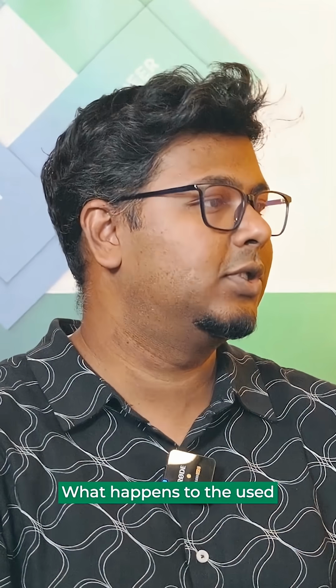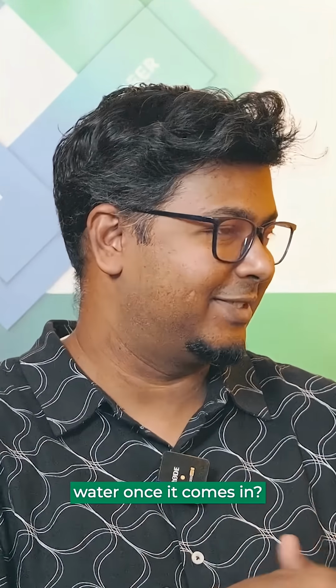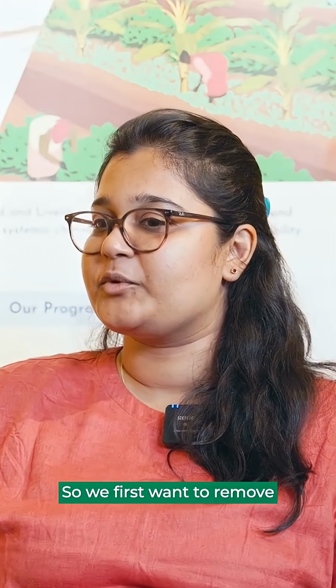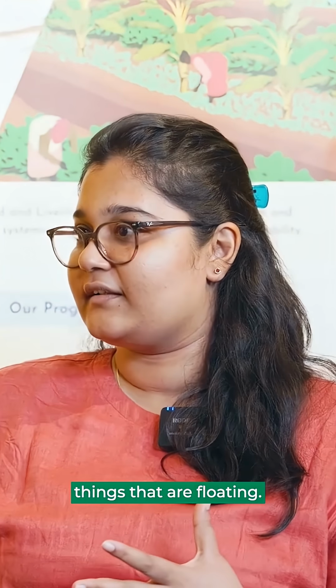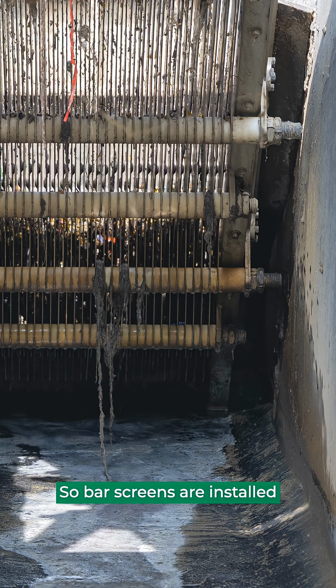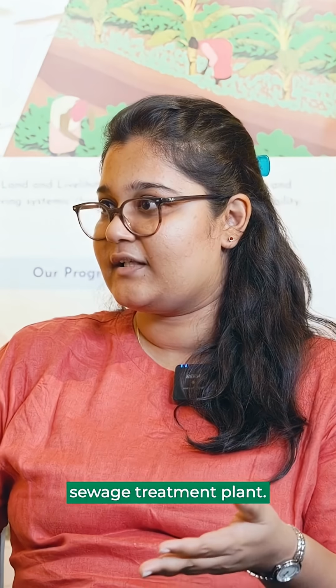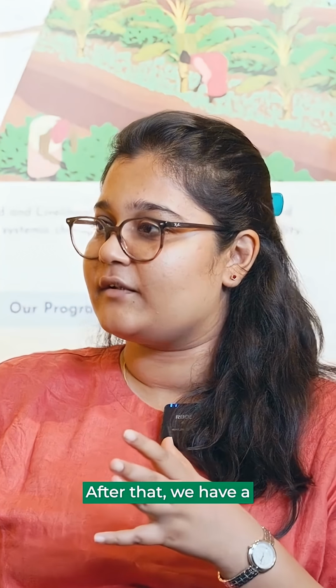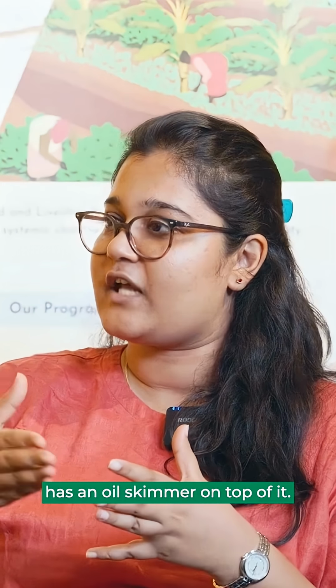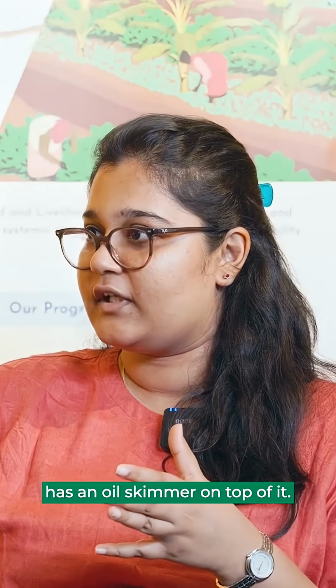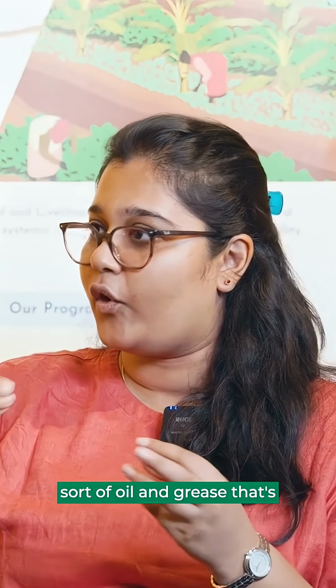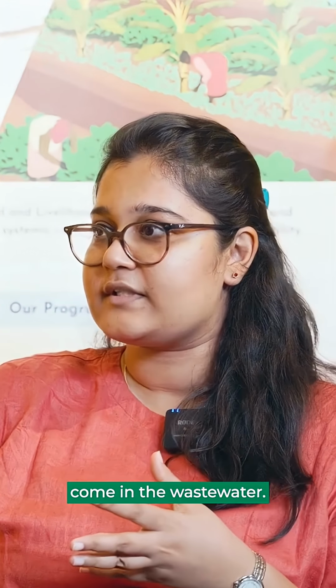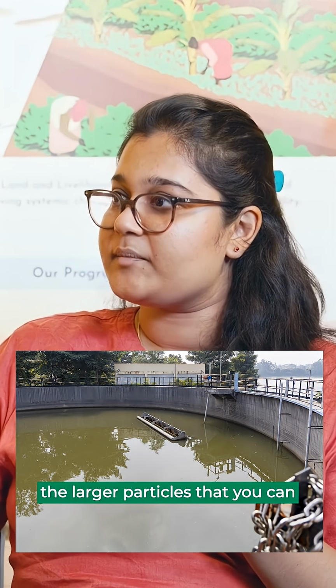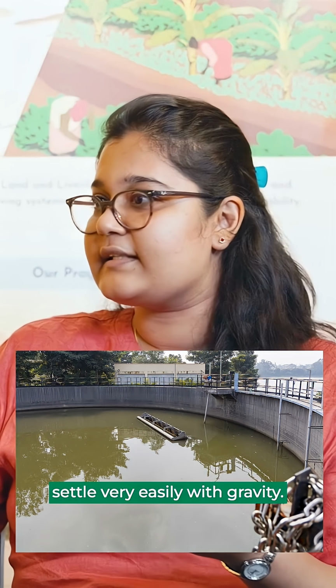What happens to the used water once it comes in? So we first want to remove things that are floating. Bar screens are installed at the entrance of the sewage treatment plant. After that, we have a sedimentation tank which has an oil skimmer on top of it. So you want to remove any sort of oil and grease that's coming in the wastewater. You also want to be able to settle the larger particles that you can settle very easily with gravity.